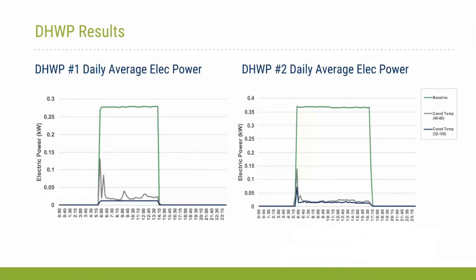So this is a graph that just shows the daily average load profiles for the pumps over the monitoring period. The green line is what the baseline pump looks like. For any constant volume air handling unit or constant volume pumping system, what you'll see is essentially just a flat line. As soon as the pump turns on, it uses the same amount of power throughout its entire operating profile. This is one of the big reasons why it's really important to move away from constant volume air handlers and constant volume pumping systems, because there's no fluctuation in power based on the actual load of the system.